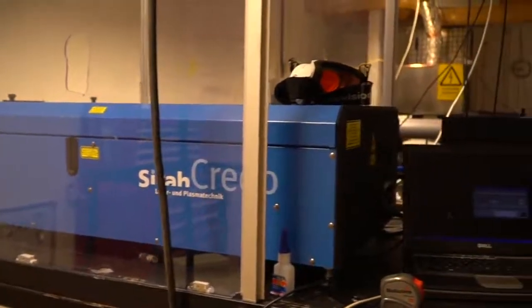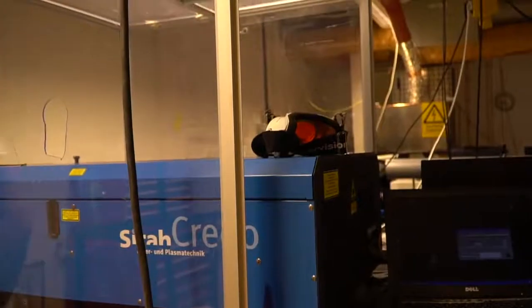The exposure limit that the naked eye can handle before protective eyewear must be worn is known as the maximum permissible exposure, or MPE limit, and depends on the wavelength of the light involved, the power of the beam, the pulse duration, and the laser beam properties.